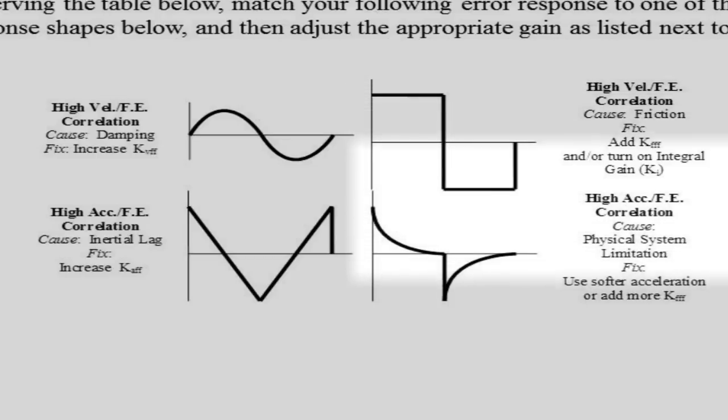The bottom right diagram shows a physical system limitation. In this case you are probably subjecting the motor to too strong of an acceleration for your system's capabilities, but you can also try adding kAFF to correct for this.